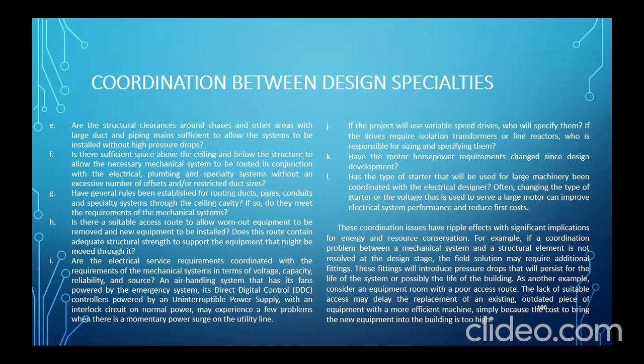An air handling system that has its fan powered by the emergency system, and its direct digital control, DDC, controller powered by a UPS or uninterruptible power supply with an interlock circuit on a normal power, may experience a few problems when there is a momentary power loss on the utility line. J. If the project will use variable speed drives, who will specify them? If the drives require isolation transformers or line reactors, who is responsible for sizing and specifying them? Okay. Have the motor horsepower requirements changed since design development?